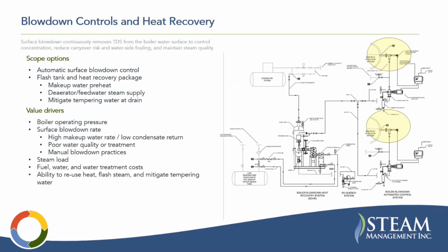Blowdown controls and heat recovery. So some scope options here are to automate surface blowdown control. For this, we are talking about surface blowdown. So that is a point at the surface level of the boiler water. Those are steam drums represented there, here, and here. But surface blowdown continuously removes total dissolved solids from the boiler water surface to control concentration, reduce carryover risk and waterside fouling, and maintain steam quality. So one scope option is to automate that process.